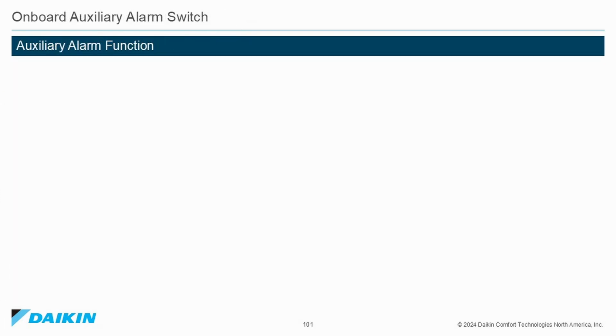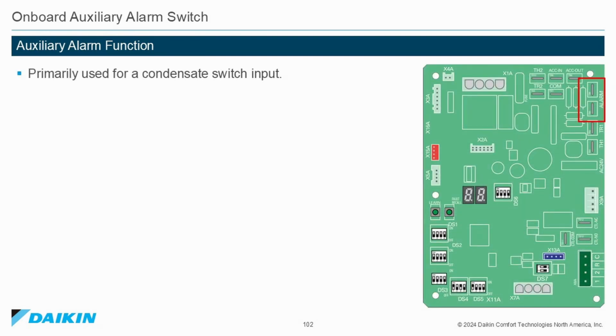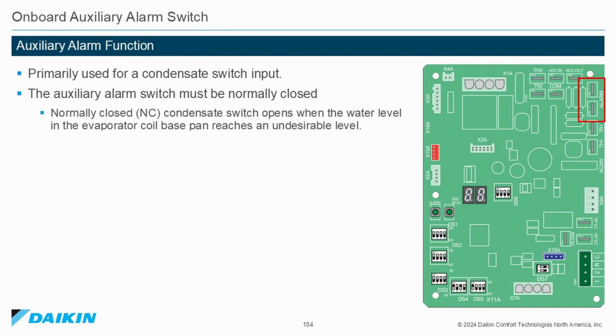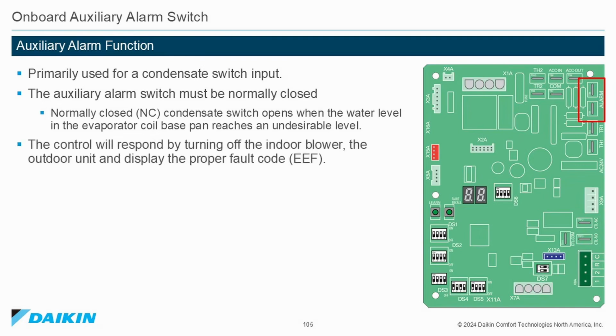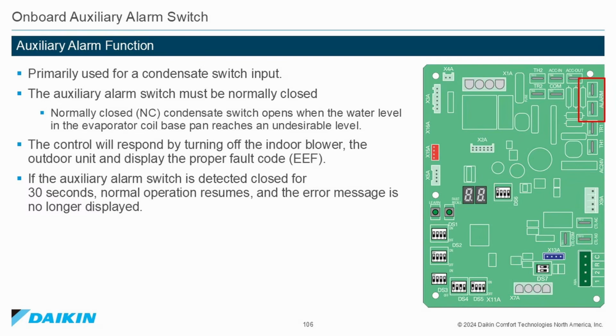Onboard auxiliary alarm switch. The auxiliary alarm function is primarily used for condensate switch input. The auxiliary alarm switch must be normally closed. A normally closed condensate switch opens when the water level in the evaporator coil base pan reaches an undesirable level. The control will respond by turning off the indoor blower, the outdoor unit, and display the proper fault code EEF. If the auxiliary alarm switch is detected closed for 30 seconds, normal operation resumes and the error message is no longer displayed.